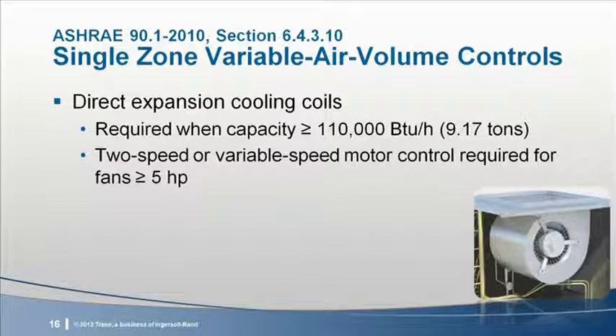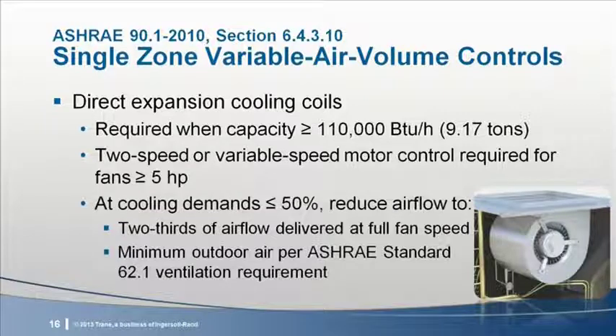As for chilled water equipment, the standard allows DX equipment to use either a 2-speed motor or a variable speed drive on the supply fan. However, the turn-down threshold is less stringent. For DX equipment operating at cooling demands less than or equal to 50%, the supply fan controls need to be able to reduce airflow to 2/3 or less of the full speed airflow.